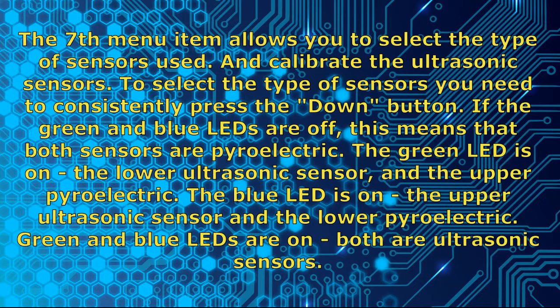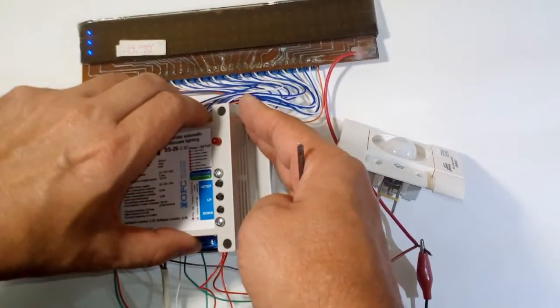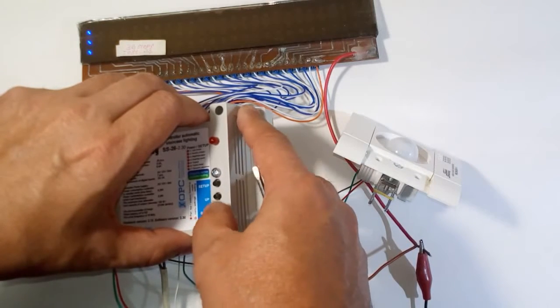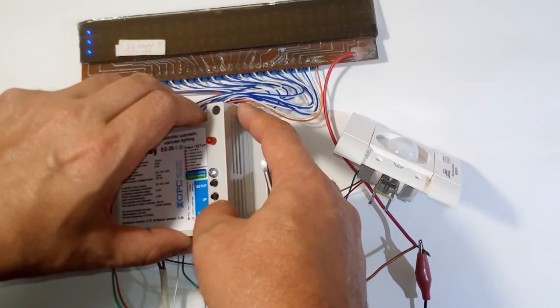Menu item 7 allows you to select the type of sensors used and calibrate the ultrasonic sensors. Press the down button to cycle through options: if the green and blue LEDs are off, both sensors are pyroelectric; green LED on means the lower sensor is ultrasonic and the upper is pyroelectric; blue LED on means the upper sensor is ultrasonic and the lower is pyroelectric; both LEDs on means both are ultrasonic. We now turn off both LEDs, selecting pyroelectric sensors.